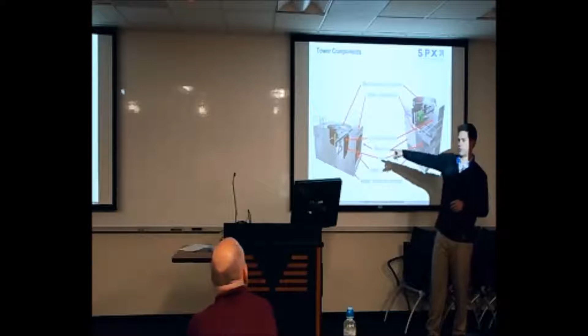So yes, keeping the motor dry is one purpose. But these fans are pretty powerful, and they can actually pull up some of that water in the system and blow it out into the air. It's not a huge problem for air quality, but where we run into problems with drift is when you have parking near these cooling towers, or even a doctor's office. Doctors with nice cars get little specks on their cars, they need to be cleaned, and they get upset and call us. So to avoid that, we put in these drift eliminators, which are triple pass, so that water cannot escape the tower and get outside the fan.